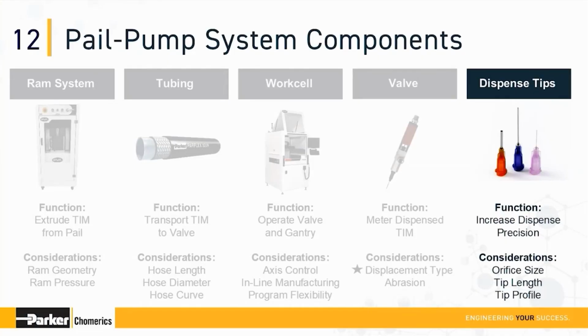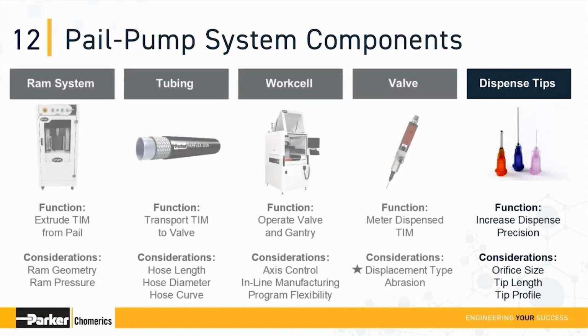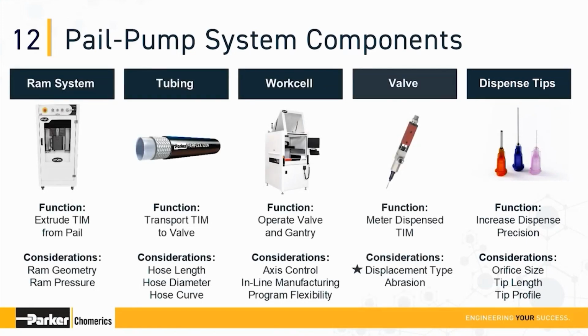Dispense tips can reduce the flow rate of the thermal gel and may alter the properties of the material, so we advise against using a dispensing tip unless it is necessary to avoid interference with a raised feature of the part. Additionally, it's best to avoid tips with long, straight walls or curves. Our applications engineering department has several of these systems in-house, so please don't hesitate to reach out if you have any questions about these components.